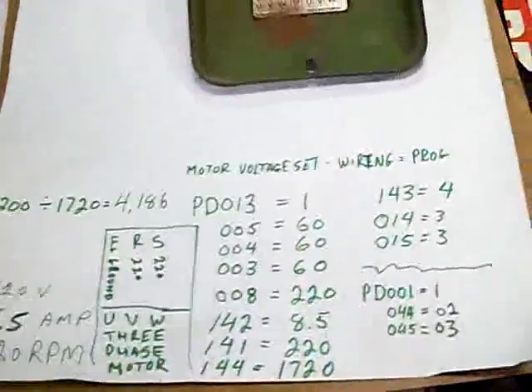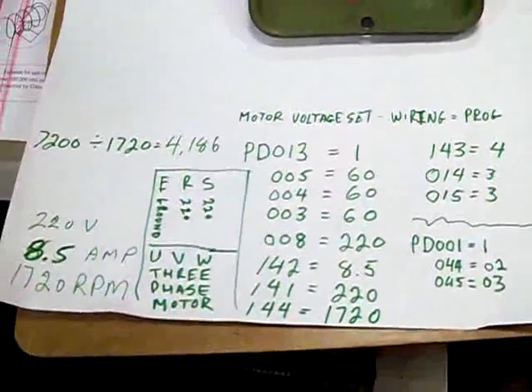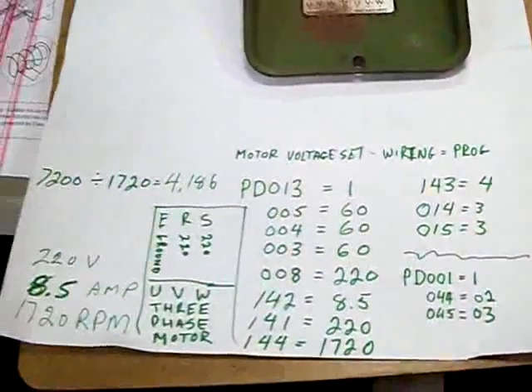These are the parameters. 13 you want to start off with, basically restores the factory defaults. 05, that's 60Hz for your max frequency. You can set faster, it'll rev the motor quicker.